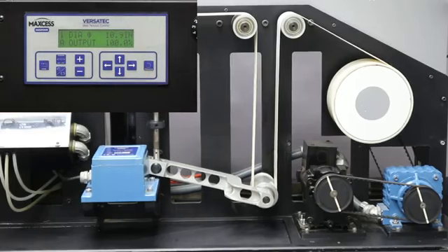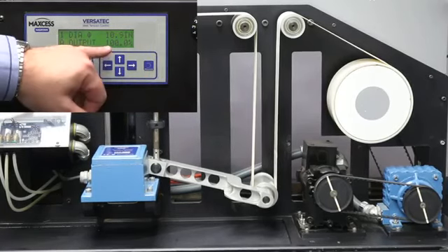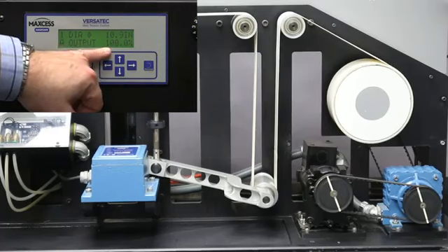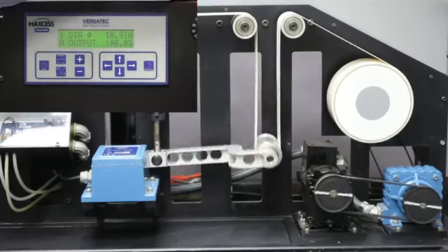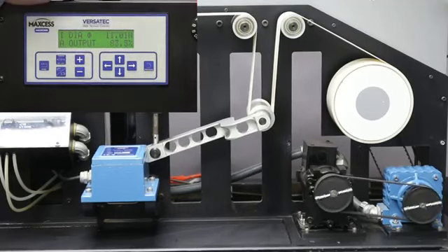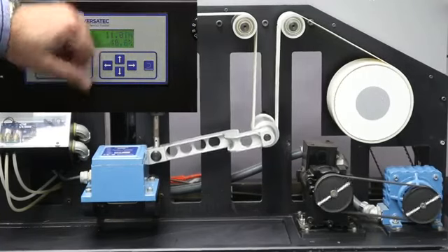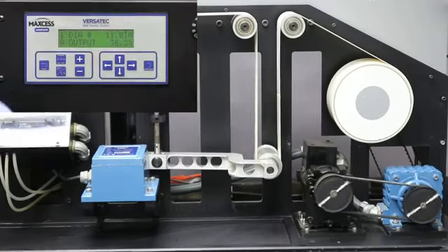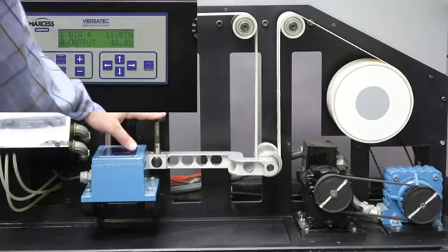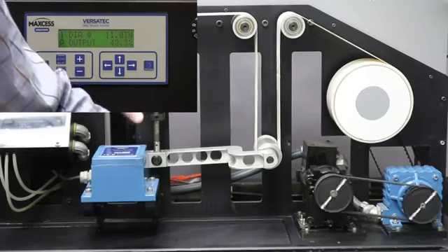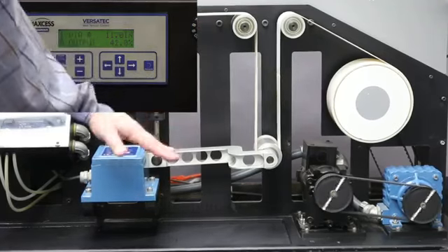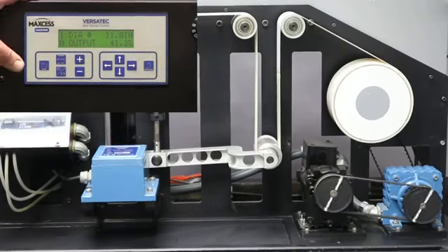Didn't turn the control loop off. Now when he goes to turn that machine back on, look where our output has gone. It's gone clear back up to 100%. And watch what the arm does when I turn it back on. Now my arm has gone up, hit the top stop, until it can integrate back down to that point. And as soon as I hit that stop, I have lost my tension control. Remember, it's only a tension control if it's not hitting the top stop or the bottom stop.